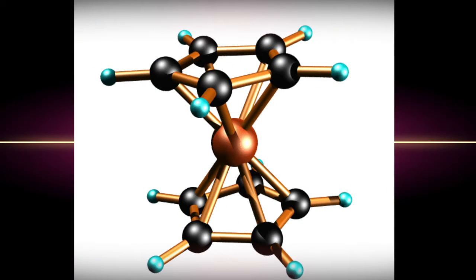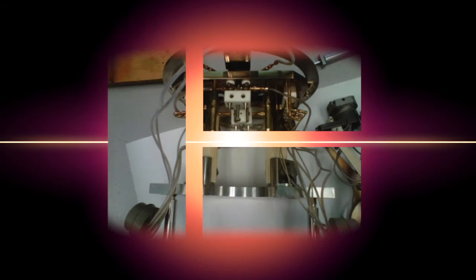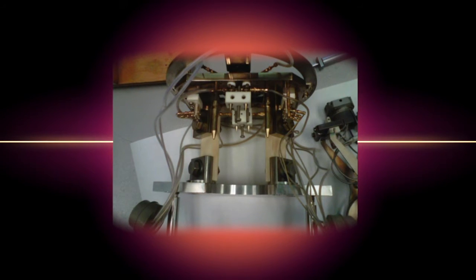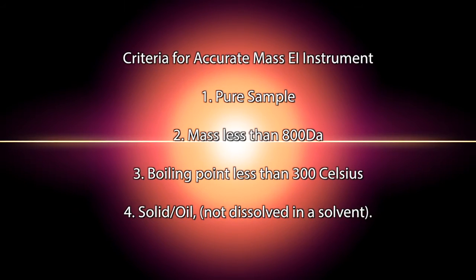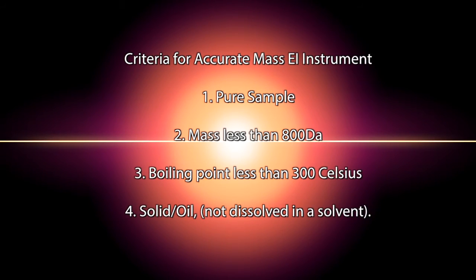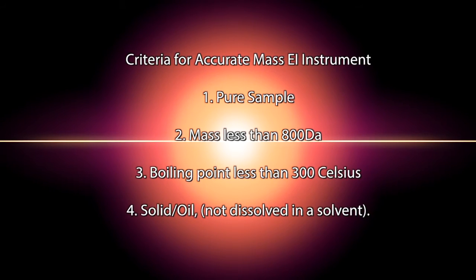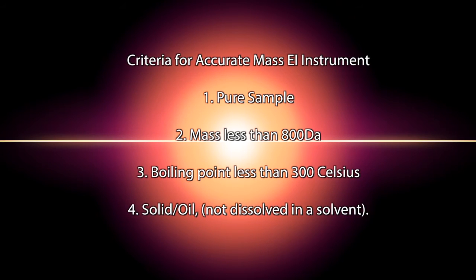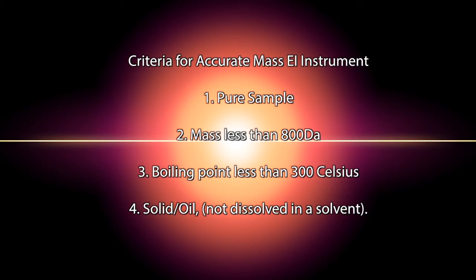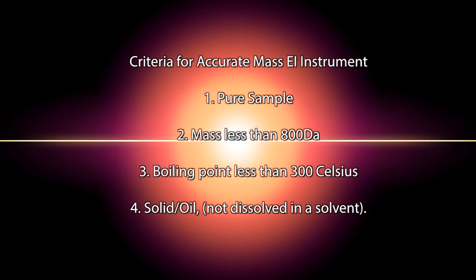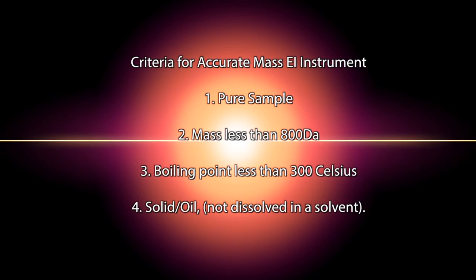If you have an organometallic compound or something that is slightly unusual or you're unsure of, please talk to me. The Concept source block has a heater that runs to about 300 degrees centigrade. So if your sample has a boiling point higher than this, your sample will not go into the gas phase, so please use another method of MS analysis, maybe electrospray. And the magnet will scan to approximately 800 Dalton. Again, if your mass is higher than this, use a different method. The sample must also be pure. There is no pre-separation technique on this instrument, so the sample must be pure. If you have a mixture of compounds, use the GCMS instead.